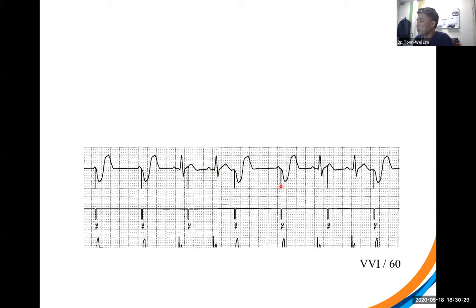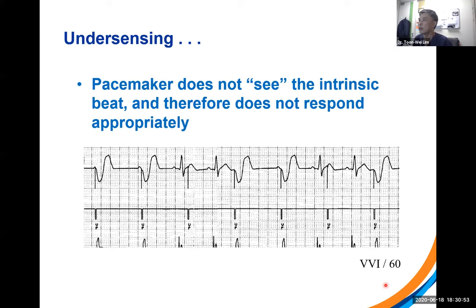Later on, you see again there's a pacing spike with the QRS, a pacing spike that comes very shortly after a QRS, and then it repeats the pattern again. What you'll notice, of course, is that the V pace intervals are completely regular across this whole strip. So this is consistent with undersensing, because the device is basically pacing at VVI 60 without any regard to what's going on in the heart. Therefore, the pacemaker has failed to see the intrinsic beat and doesn't pace appropriately.